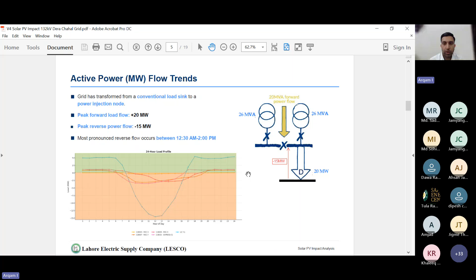With just 40 megawatts installed in the system, we have been experiencing reverse power flows from the rooftops to the substation during the daytime, once the solar PV systems are generating at peak. If we look at this curve, this is the cumulative curve of the whole substation. In the early hours we have 5 megawatts, and late in the night hours, when the sun is not available and all the power is supplied from the grid, we have 20 megawatts being supplied to the load. But during the day, we have this huge reverse power flow coming from the solar PV systems to the substation, and then going upstream into the transmission network.